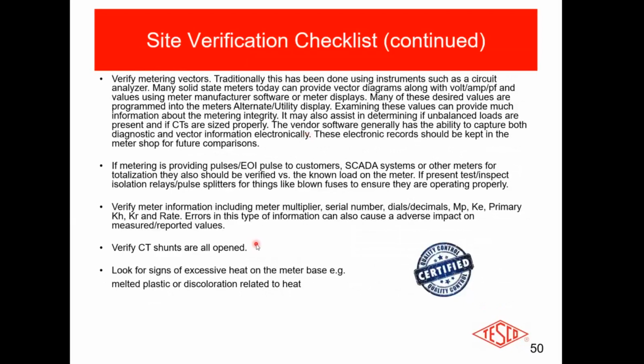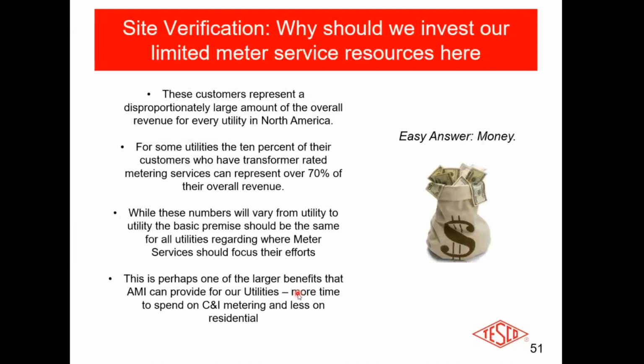All right? If you see signs of excessive heat, if you see wires that clearly had overheated, that could be a sign of a problem. If you see issues at the meter base, that could be signs of a problem. Anytime you see melted plastic or discolored wires or anything, it's obviously related to heat. What went wrong? Okay? Why are we checking these?